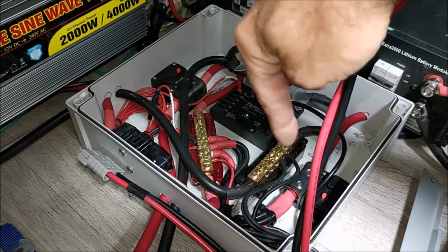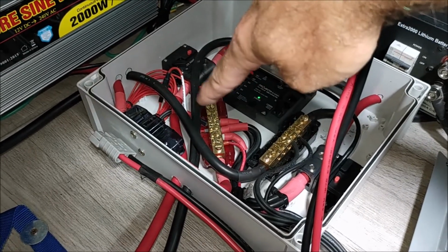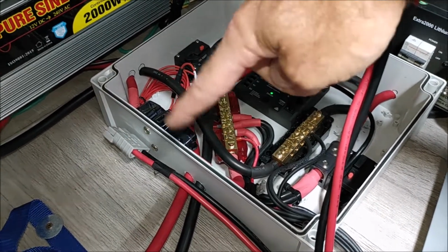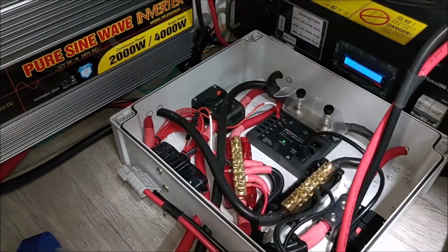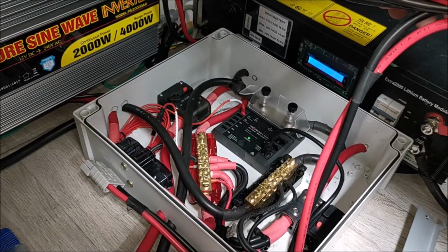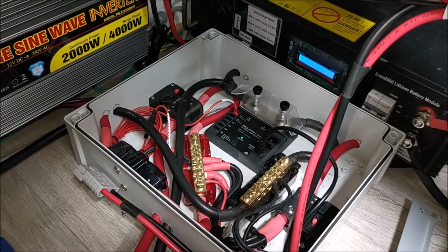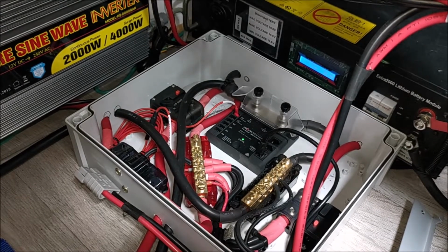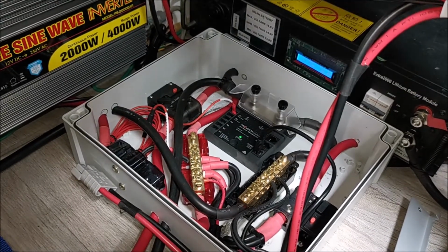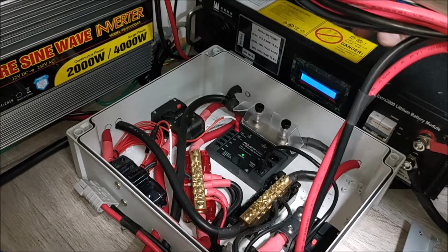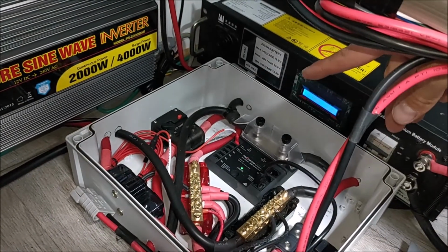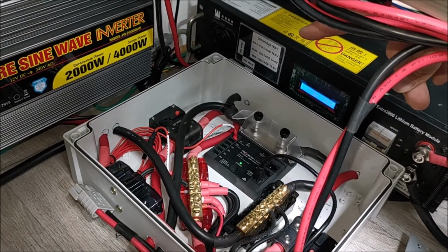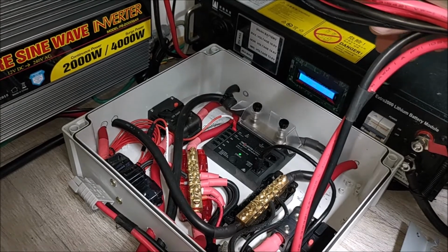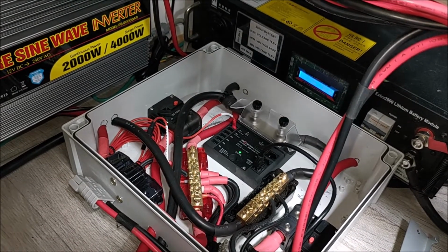I've put them through breakers, and they run direct to this busbar, which then runs the inverter. That's just the way I've set this up. It's not ideal to not have them coming through the BMS, but as long as the unit balances the charge while it's charging these batteries, I'm happy with that.